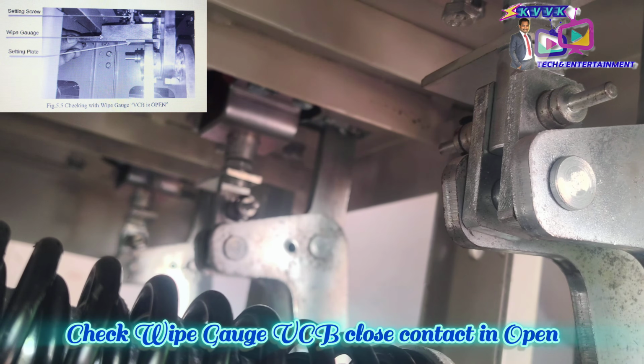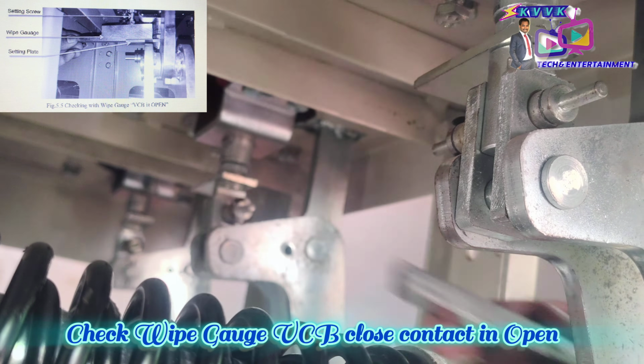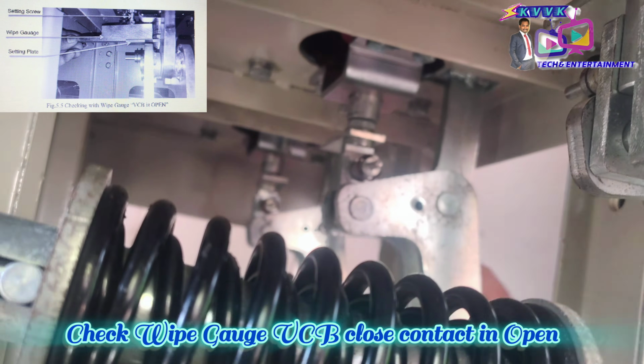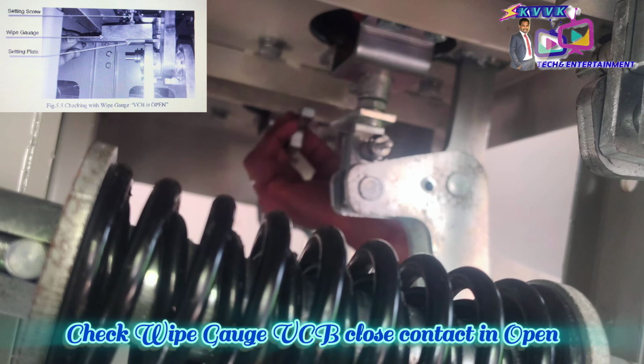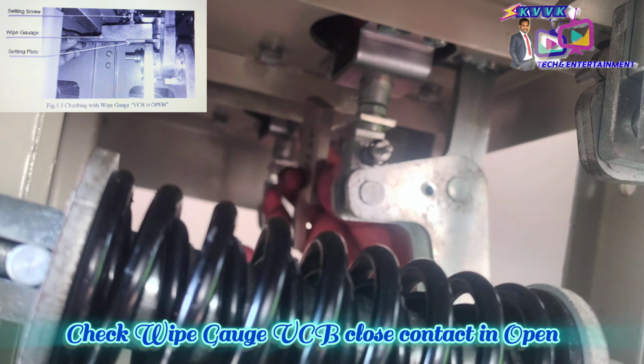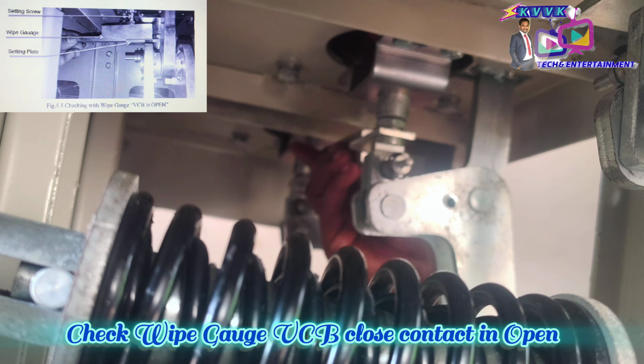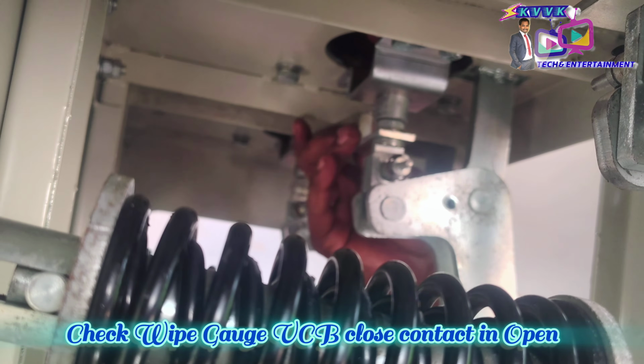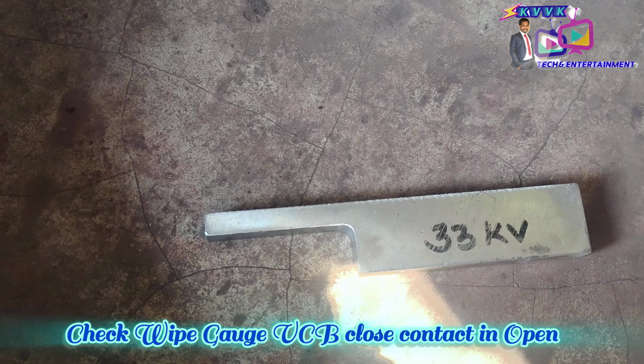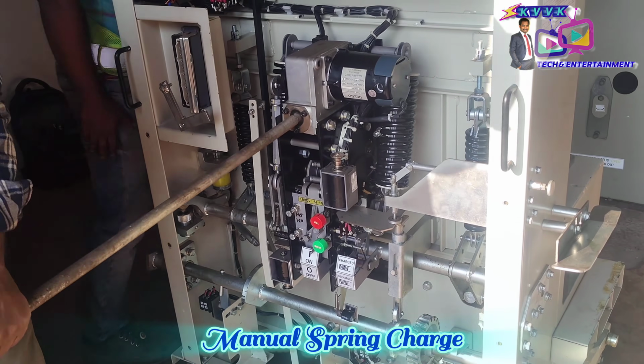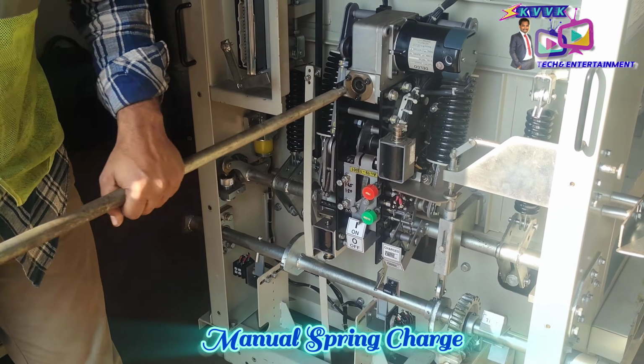As I said earlier, we have to check the gap for the VCB closed contact in open condition. For gap adjustment, we can tighten and loosen the assembly. After checking in open position, we have to do spring charge and close the VCB.